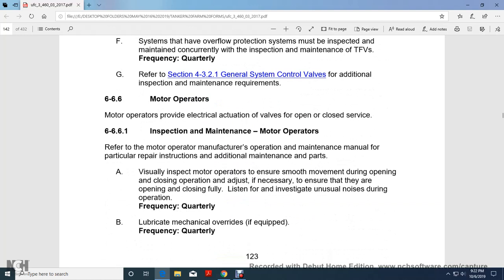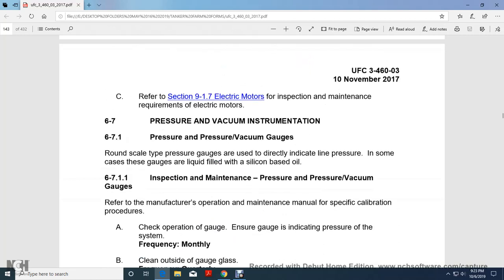Motor operators, 6.6.6. Motor operators provide actuation of the valve to open and close. 6.6.6.1, inspection and maintenance for the motor operator. Refer to the motor operator manufacturer's operation and maintenance manual for particular repair instructions, additional maintenance and parts. Visually inspect the motor operator to ensure smooth movement during the opening and closing operation, adjusting as necessary. Ensure that it is opening and closing fully, and listen for and investigate unusual noise during operation. Frequency is quarterly. Lubricate and check the mechanical override, frequency quarterly. Refer to section 917, electrical motors, inspection and maintenance requirements.